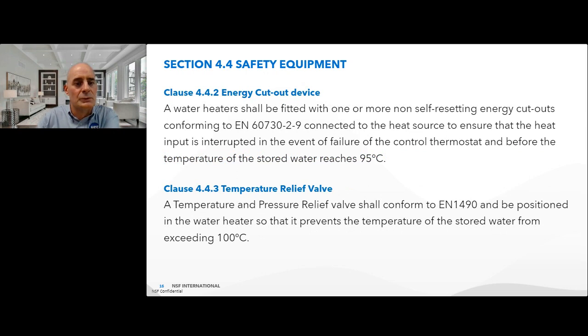Clause 442, so this covers the energy cutout device. So the water heater should be fitted with one or more non-self-resetting energy cutouts conforming to EN 60730-2-9, connected to the heat source to ensure that the heat input is interrupted in the event of failure of the control thermostat and before the temperature of the stored water reaches 95 degrees.